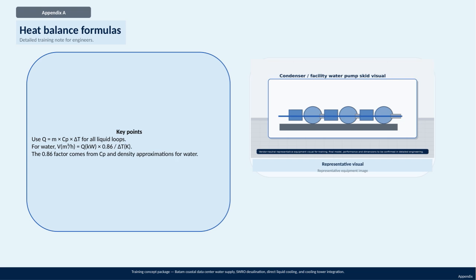For water specifically, we use a volumetric flow rate formula. V in cubic meters per hour equals Q in kilowatts multiplied by 0.86 divided by delta T in Kelvin. The 0.86 factor is derived from typical values for water's specific heat capacity and density, making these calculations more straightforward.